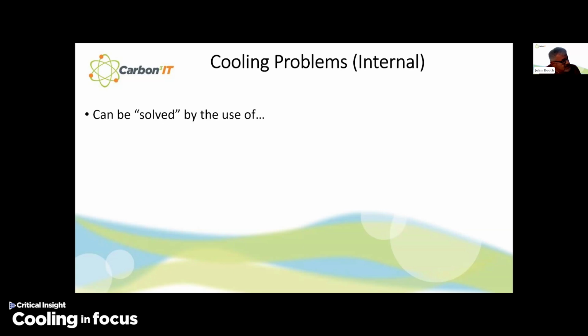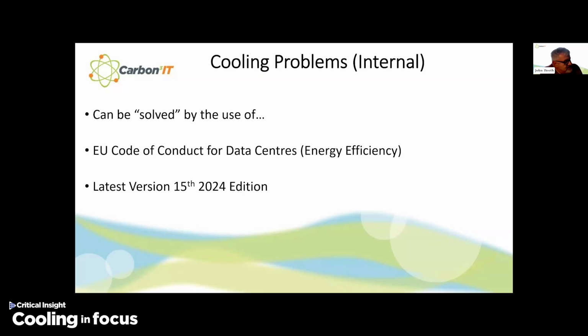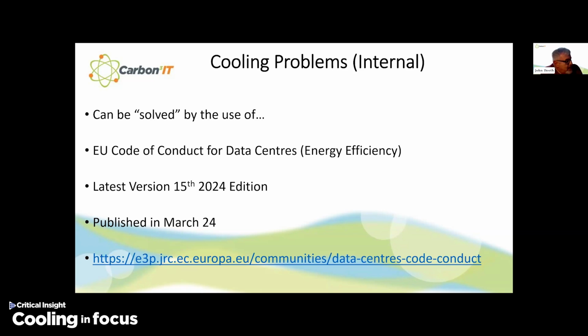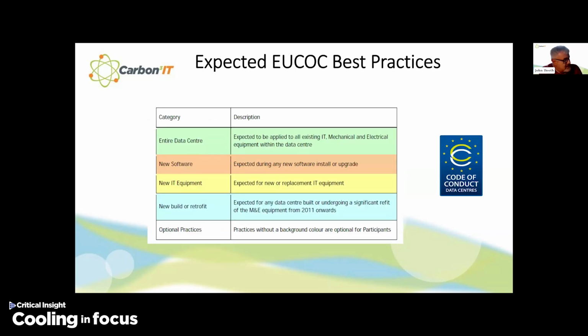But both of those problems can be solved by the use of the EU Code of Conduct for Data Center Energy Efficiency. And the latest version is the 15th edition, 2024, which was published probably 4 weeks ago and is available on this link. It contains 53 best practices. So just a reminder, if you download the publication and look through it, there are expected best practices depending on where you are in your cycle. So if there's a green best practice, it's expected to be applied to all. If it's new software, it'll be orange, new IT equipment will be yellow, and if you're doing a new build or retrofit, you're expected to do the best practices that are for the M&E, and the optional ones are in white. So let's quickly go through them.